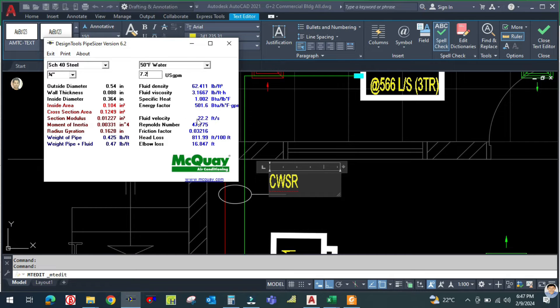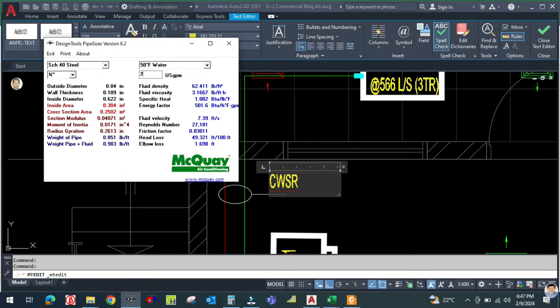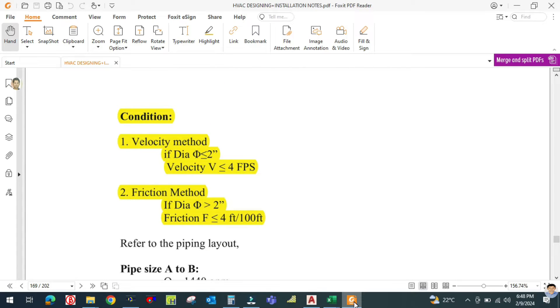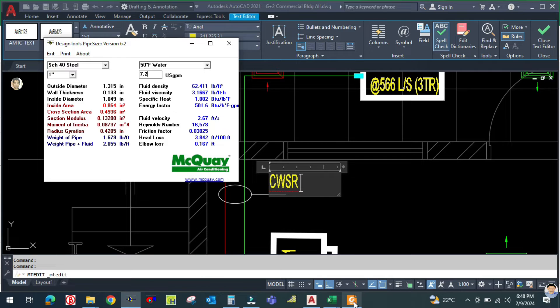For ¼ inch the velocity is 22 feet per second — not acceptable. Increase to ½ inch: velocity is 7.6 feet per second — still not acceptable, must be less than 4. Check 1 inch at 7.2 GPM: velocity is 2.67 feet per second, which is less than 4 feet per second — that is acceptable.